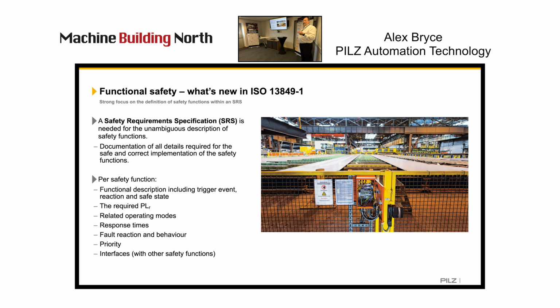So you need to detail what the machine's supposed to do, how it's supposed to do it, what performance requirements you've got around the systems, how it should react during fault conditions, what we need to shut down, whether we stop everything or only a certain part, and whether we can leave certain power on to various actuators or whatever it might be. There's a requirement there for that.